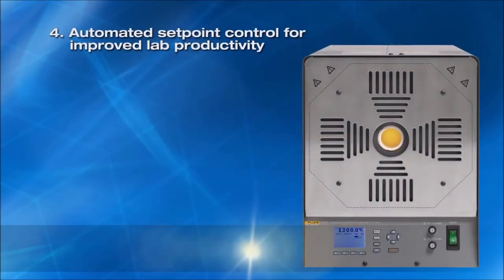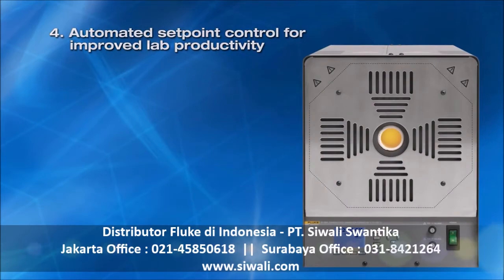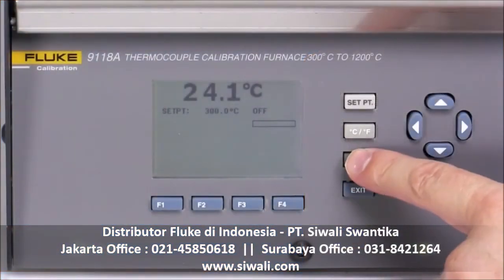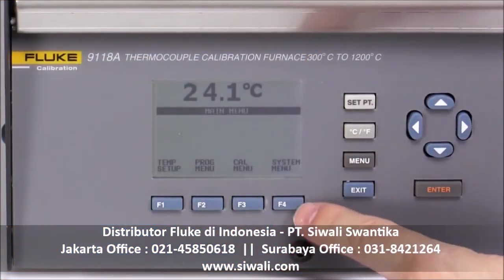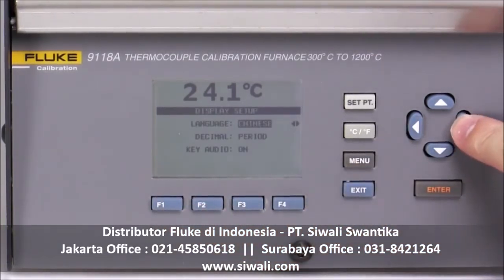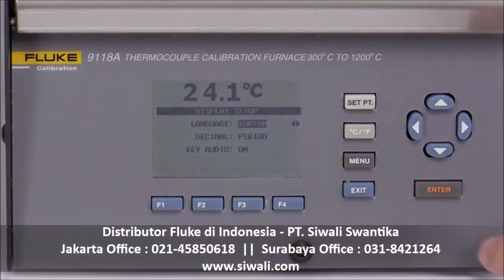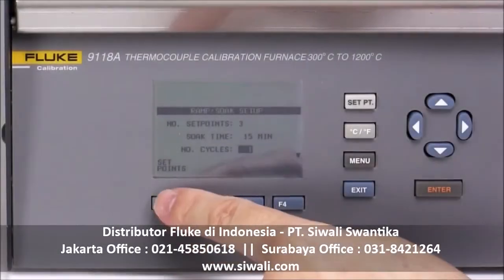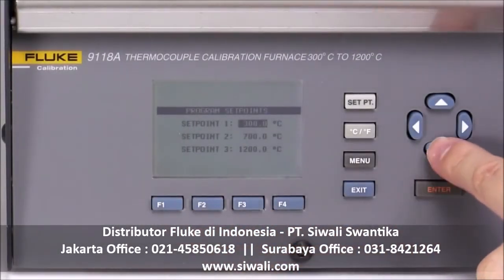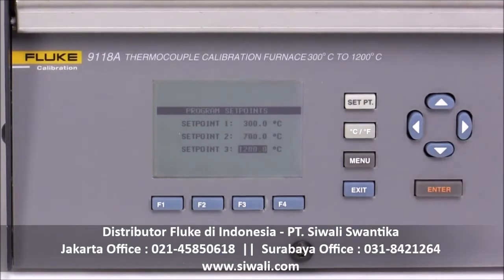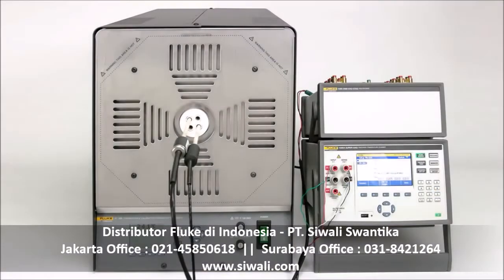Fourth, automated set point control. The 9118A uses a proprietary programmable controller with user-selectable interface prompts available in 9 languages. The controller helps technicians improve lab productivity by automating set point temperature control for up to 8 set point temperatures, the time duration the furnace controls at each set point, and the temperature ramp rate.